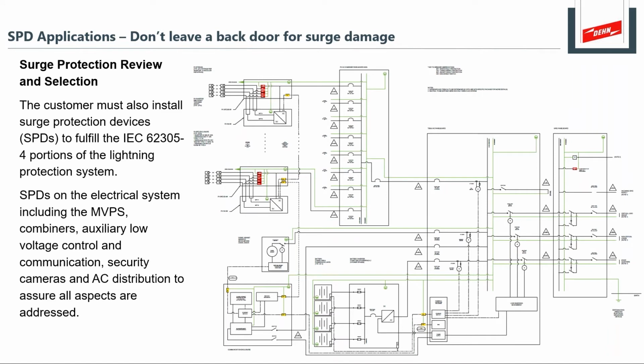So that leads us to the next pillars of protection, the equipotential bonding and the surge protection. So here we have a diagram for power generation at a solar plant. And what's important about this is that you can see that you'll have SPDs applied on the high power DC collection at the actual string inverters and at the solar panels, but you'll also have surge protection applied on the data collection. The data network is just as important on these types of power generation facilities. You have to monitor all the various processes to make sure that the power plant is running efficiently.